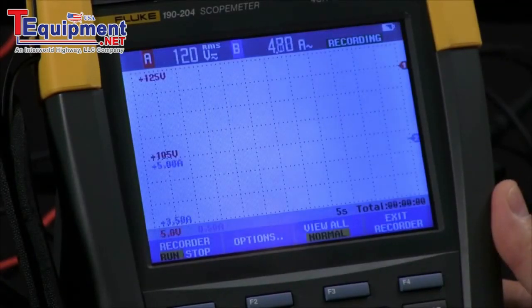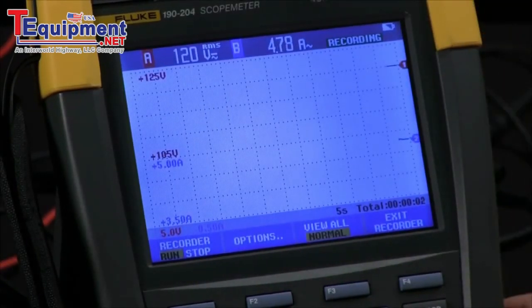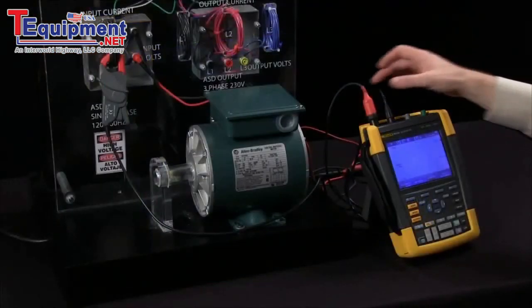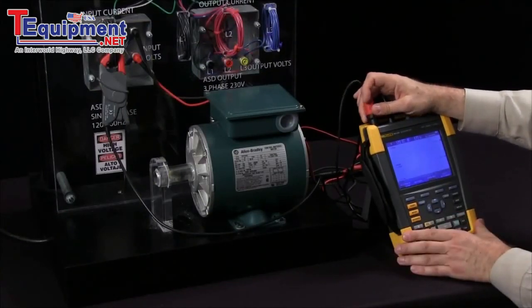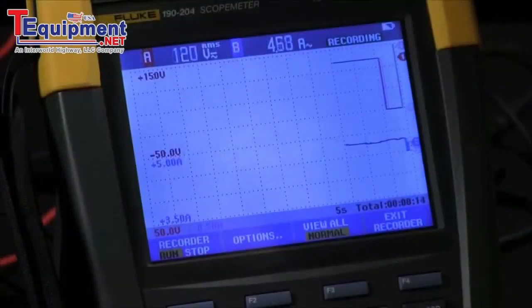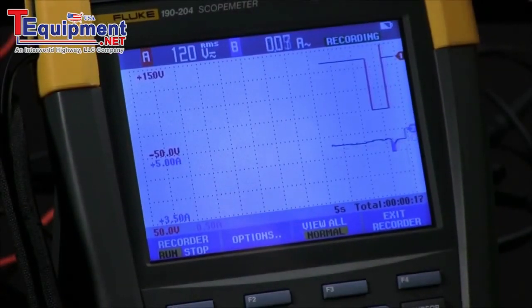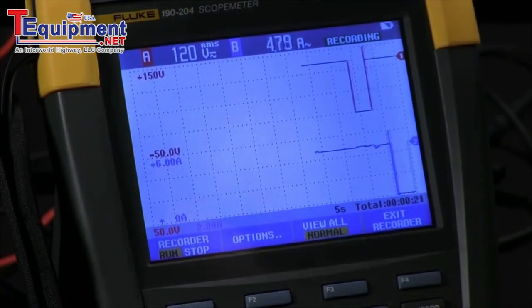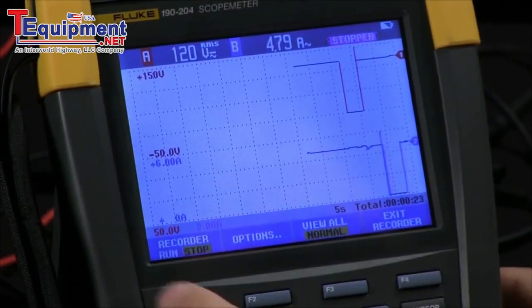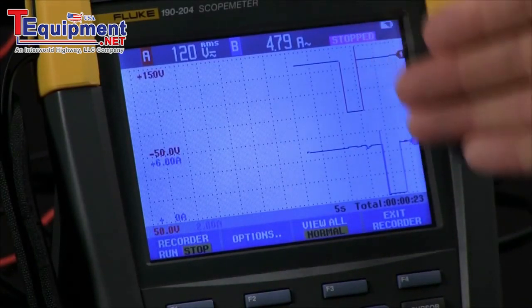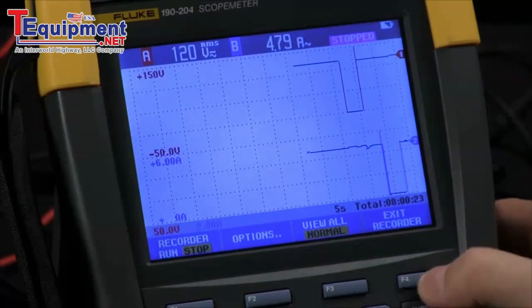To begin we simply select trend plot and you will see how we start automatically to graph a line across the screen. If we have an interruption — and I will cause that by disconnecting the probe — you see how we are dropping out on channel 1, and I can also induce a fault into channel 2. Now to look at these I can simply stop the recorder and we can see by the plot line we have clearly identified any faults in the signal.